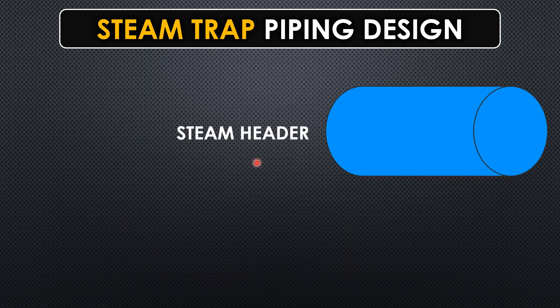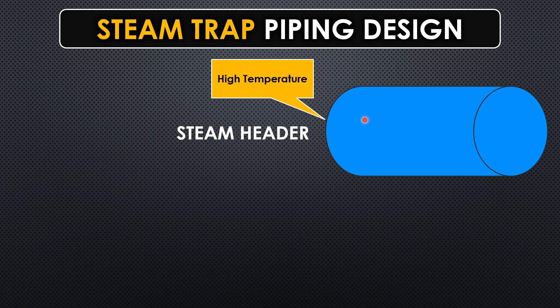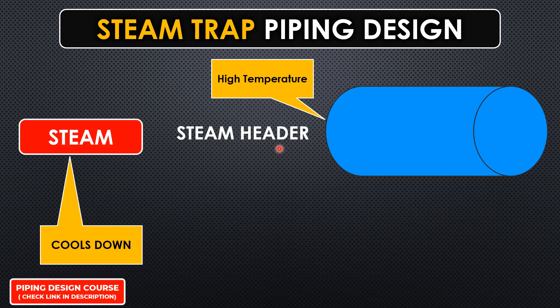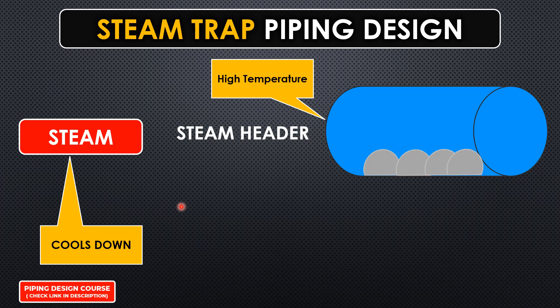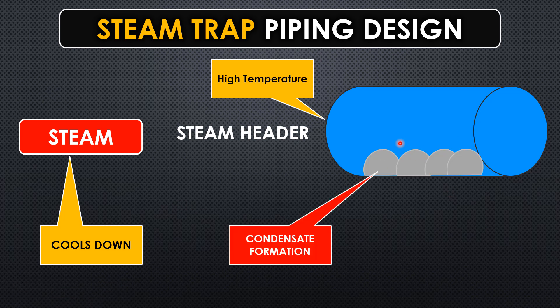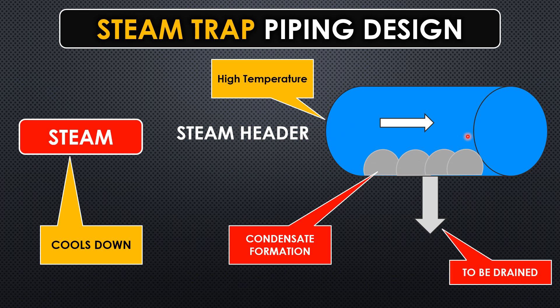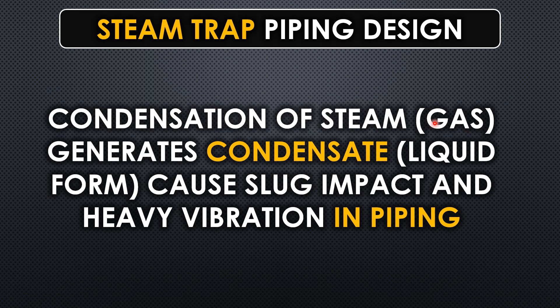In a steam header, you will find steam at high temperature, but over a period of time, after going through multiple processes, the steam cools down and becomes condensate. This condensate will travel along with the steam and keep hitting every elbow and fitting, causing vibration in the piping. Condensation of steam, which is in gas form, generates condensate in liquid form and causes slug impact and heavy vibration. It's really important to remove the condensate immediately.